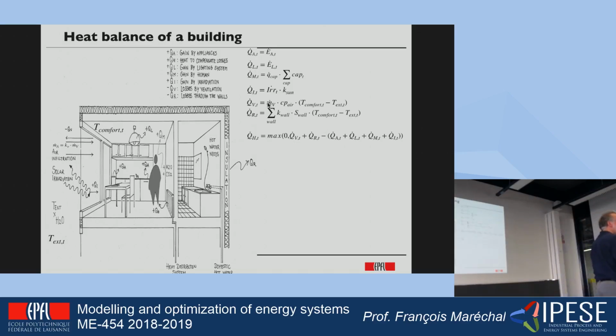If you are in a lecture room like this, I guess the renewal rate will be once an hour, while in the labs where you have the possibility of having chemicals that are evaporated, etc., the renewal rate is much higher, so up to 10.